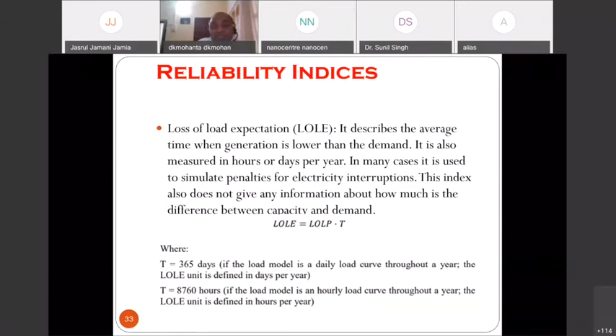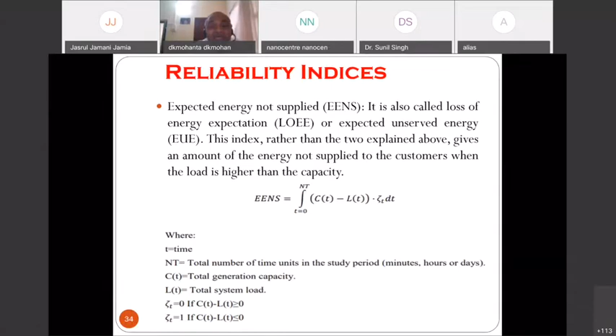So we say that 100 megawatt hour was not supplied, or 10 megawatt hour was not supplied. Here we just have a probability, which doesn't tell exactly how much energy was not served. But with ENS, we exactly know how much energy was not served. Suppose one ENS is 100 megawatt hour and another is 10 megawatt hour. Naturally, 10 megawatt hour is a more reliable system than 100 megawatt hour expected energy not served.